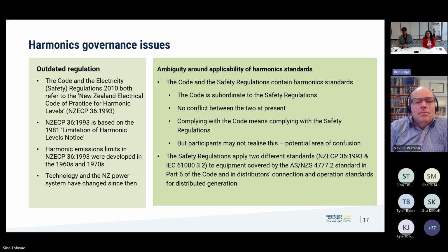There are two issues basically with the governance of harmonics. The first is that these values and limits are based on measurements done in the 1960s and 70s, caused by HVDC, motors, and other loads and generators from back then. So these are a bit outdated. Now we have more inverter-based resources like solar farms, wind farms, and BESS, so they may not be fit for that purpose.